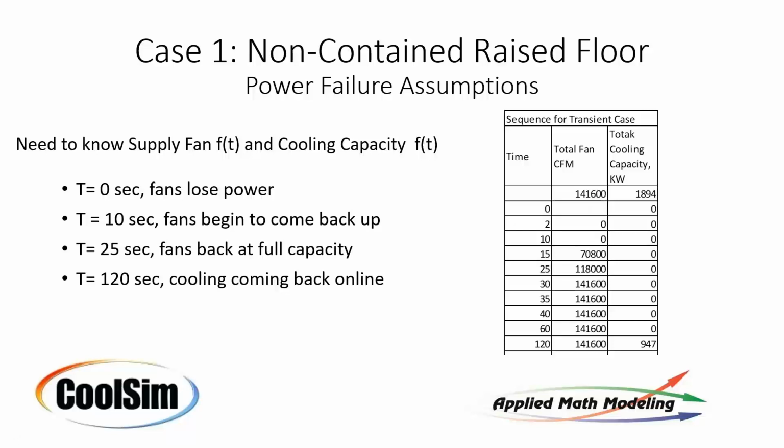So in this particular example, what we're seeing here is 10 seconds. So this is diesel generator start generally. And by the way, these things generally aren't backed up with battery. It's too expensive. So there's no UPS for the cooling system typically, although some data centers have that. So in 10 seconds, the generator's up and running. I think that's pretty generous, by the way. But the generator's up in steady state, 10 seconds.